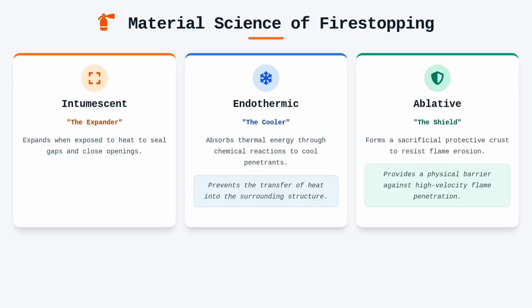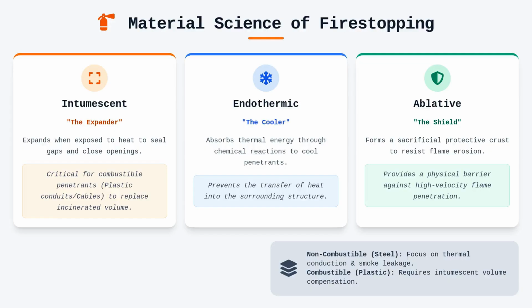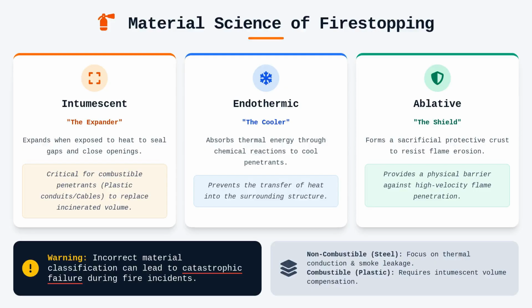When dealing with combustible penetrants, like plastic conduit or insulated copper cables, intumescent properties are usually required to compensate for the volume lost as the penetrant incinerates. For non-combustible penetrants like steel conduit, the focus shifts toward preventing thermal conduction and smoke leakage. Choosing the incorrect material classification can result in catastrophic failure during a real-world fire incident.